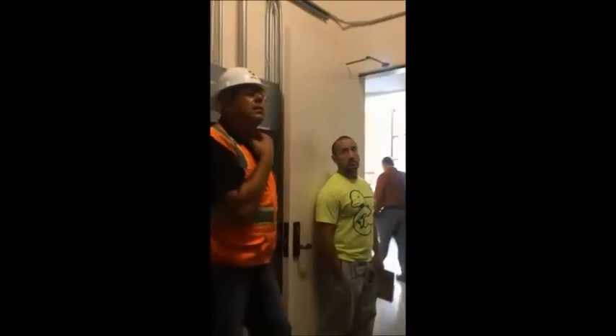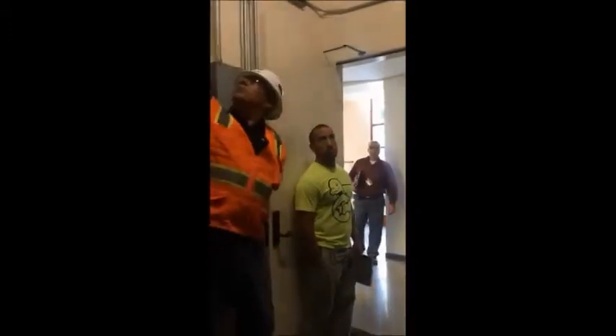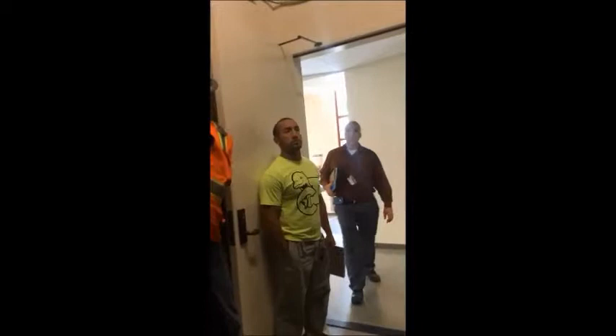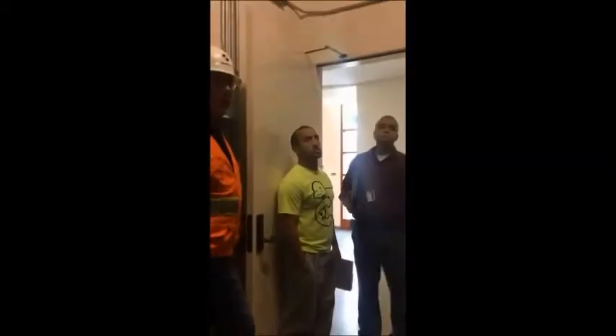It's like a ballroom in here. Originally, that evaporator unit was supposed to be above here. So that's why we moved it over here. So if there was a concern or anything, at least it drips down in the middle of the floor. But yeah, it used to be above the lighting gear. So the thermostat's there to your left.